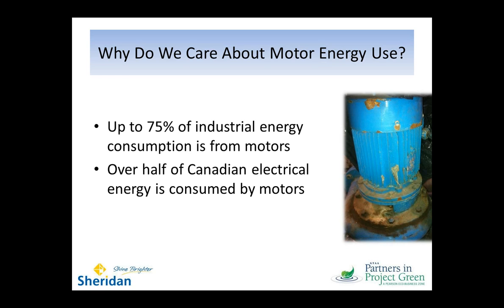The next question I guess you'd ask is, why is that number still so high? And really the reason is that motors are integrated into our manufacturing processes. And because of that, it can be very difficult to figure out what kind of loads they should be sized to do, how they could be sized smaller. It's very difficult to measure them in place. And so often what we see is motors end up being replaced on a one-to-one basis. So one goes out, another one goes in of similar specification, similar horsepower.